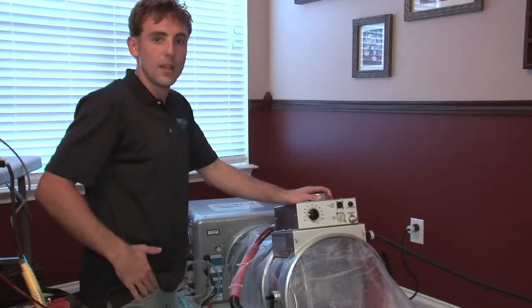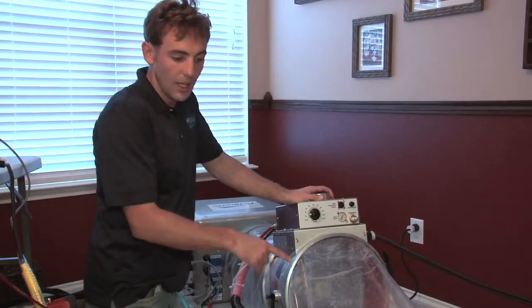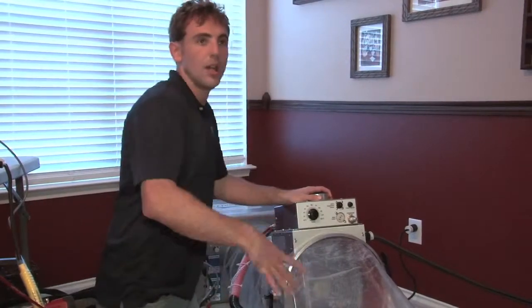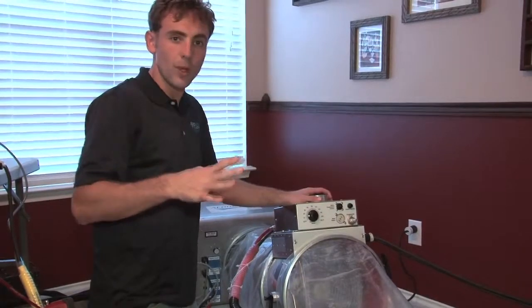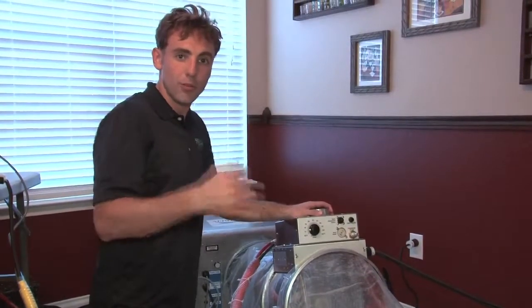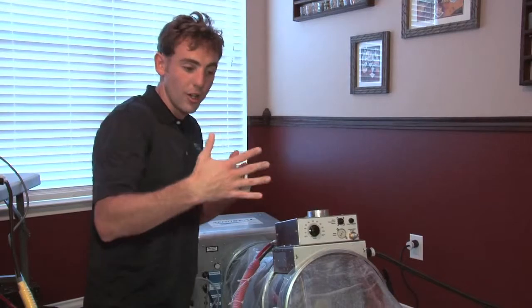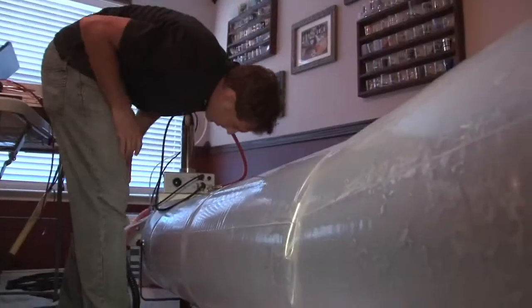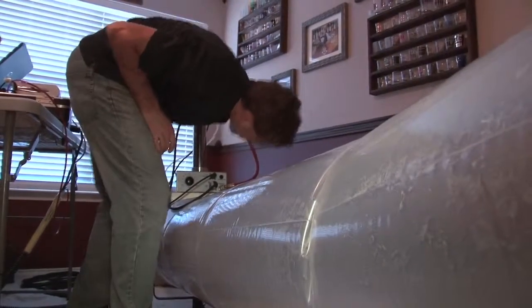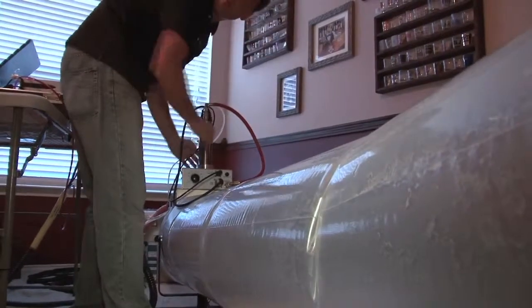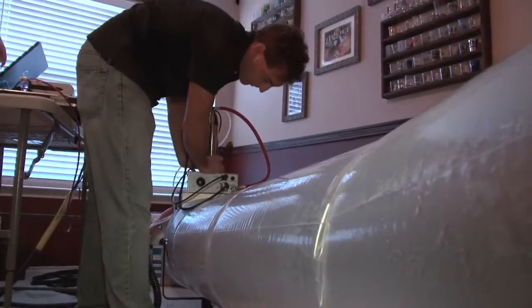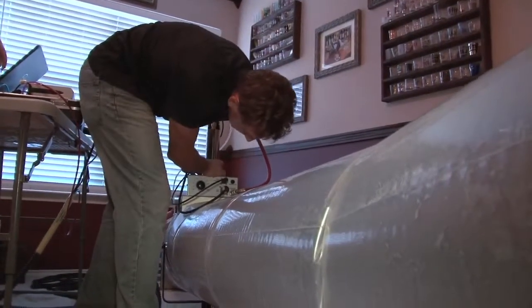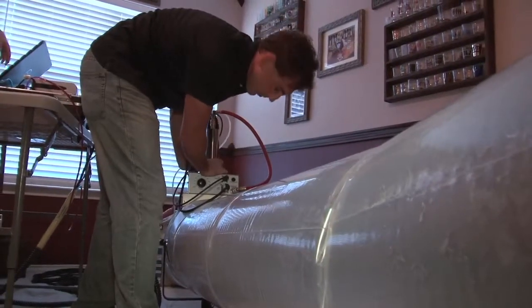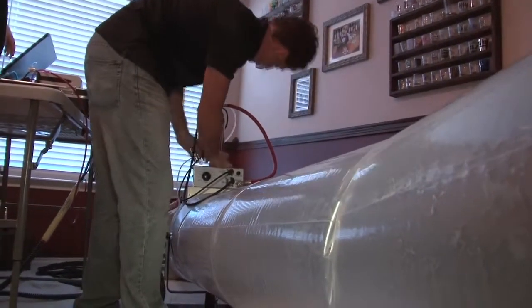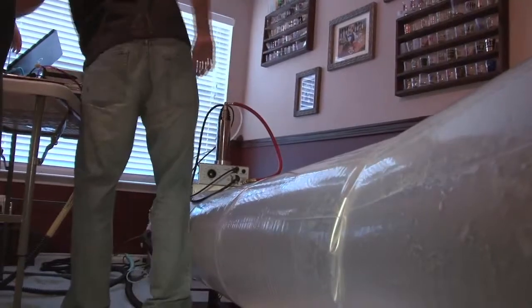So basically, when the glue becomes airborne, it goes into the duct system, and whenever there's a difference in pressure and temperature, the glue sticks to the edge of wherever that hole is, and the glue can then start building up on itself. And you'll see in the demo plenum that we have where the glue will start slowly building on itself and start to solidify.